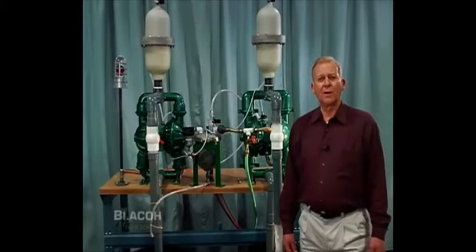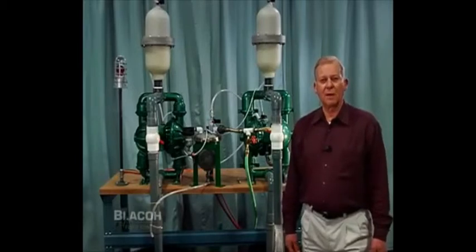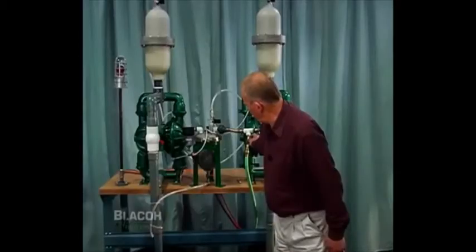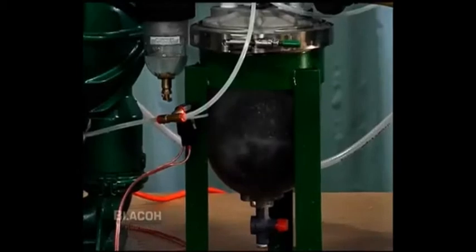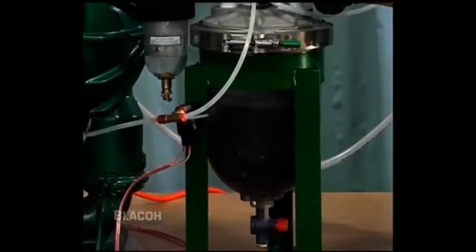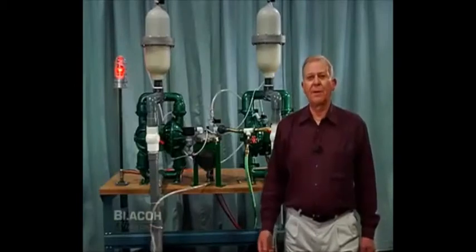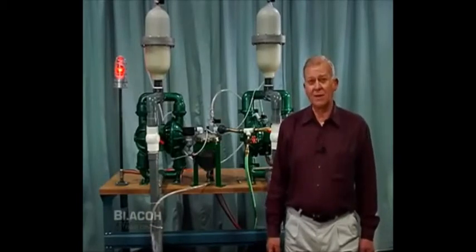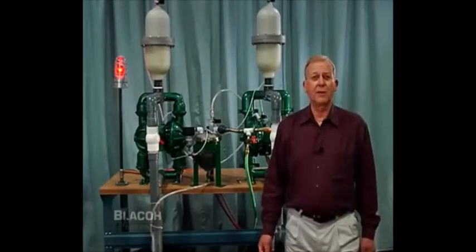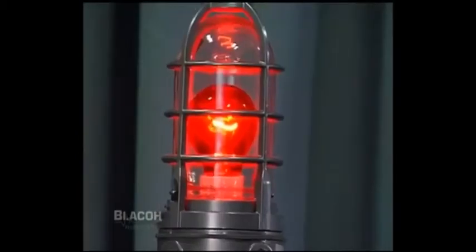When we introduce water into the primary pump's air exhaust, approximately one and a half cups of liquid enters the Spill Stop, depending upon specific gravity and viscosity. The primary pump will shut off, the standby pump will automatically turn on and energize the light alarm.